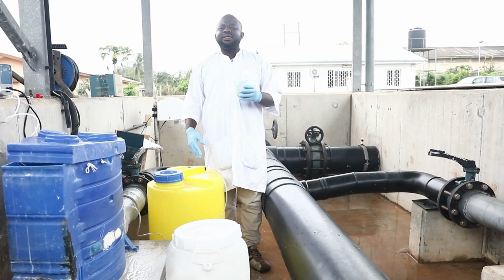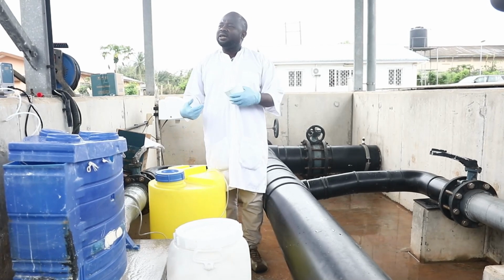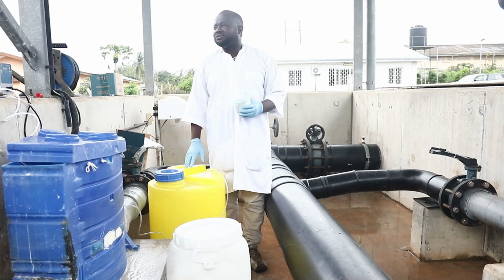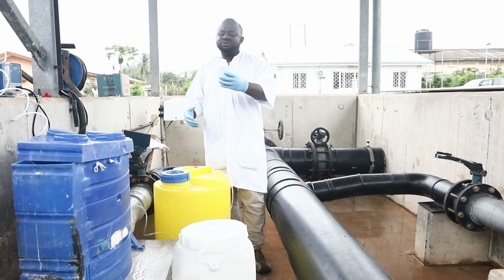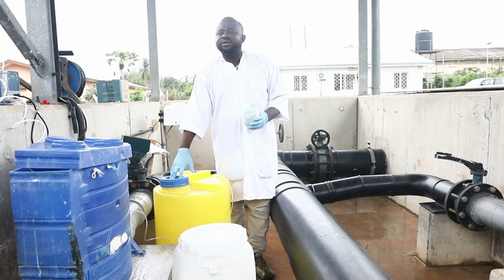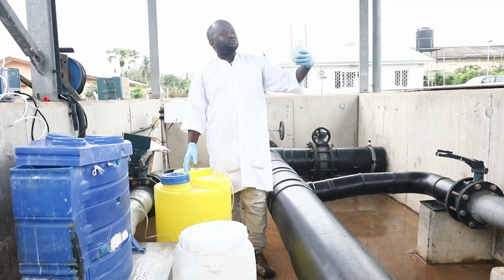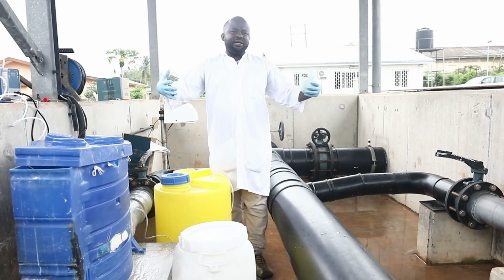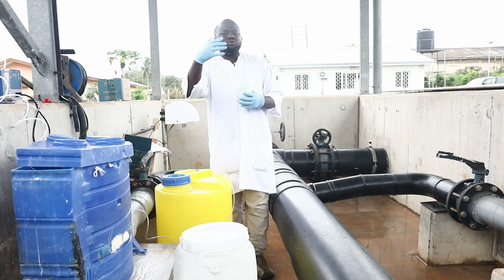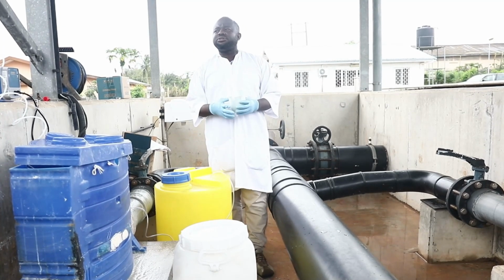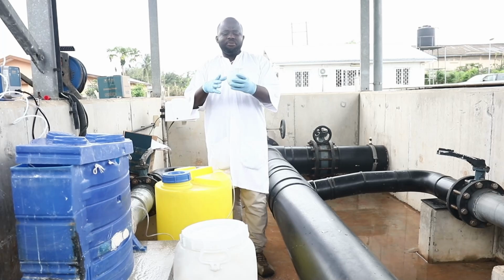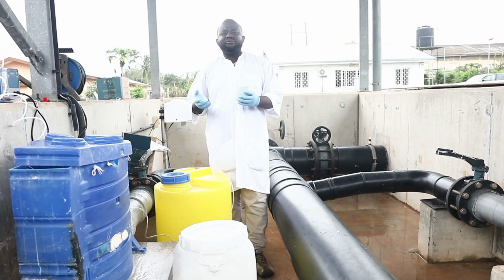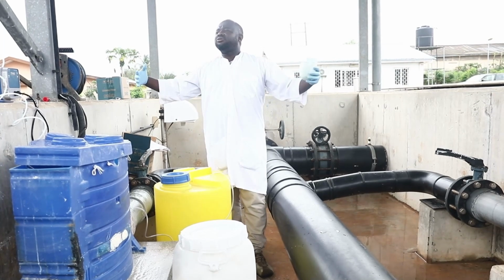But that means every day you have to come and prepare, which is also a bit of work, because you have other schedules that you need to attend to. So now we can choose to prepare a stock for 5 days. If in a day they are using 4.2 kilos, and I want 5 days, I multiply 4.2 by 5. You can see the information on your screens, how to go about the calculations, and you can follow suit. So for 5 days, that means we will measure 8 of these times 5. If you are doing it for 1 week, then we do it for 7.